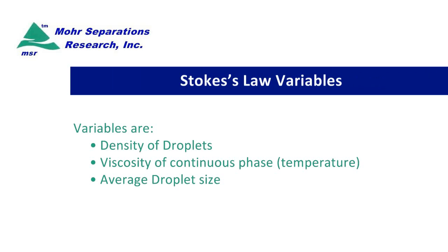The key variables are: the density of the droplets, the viscosity of the continuous phase which is the water and that's dependent upon the operating temperature, and the average droplet size — which is the biggest single variable because it's a squared function.